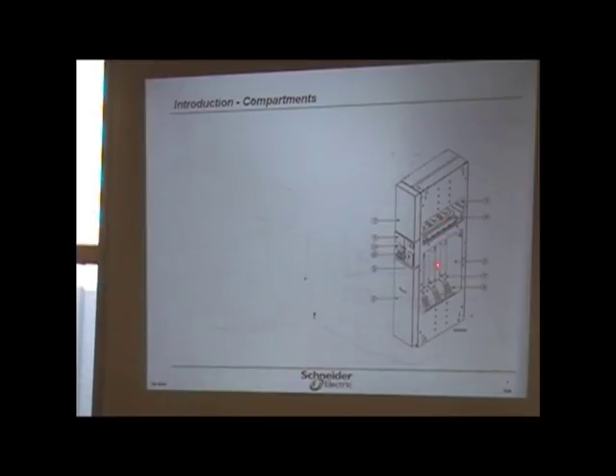It comes down to the fuses, and from the fuses, of course, these surge arresters right here. But from the fuses down here is where it goes down to your load, so your wire comes right out. It doesn't go through a set of contacts and stuff like that. So that's the difference, essentially. But it looks almost identical in the front as well, because you're going to have this high voltage compartment, the low voltage compartment at the top, and here's your controller.